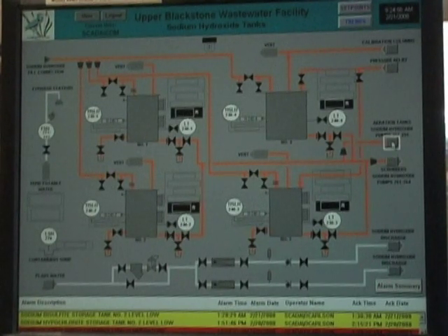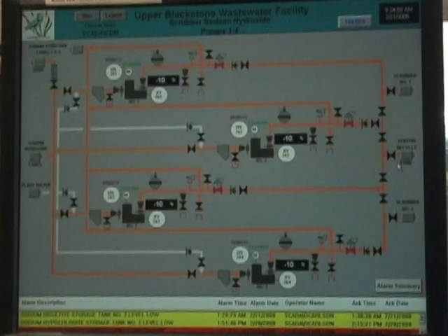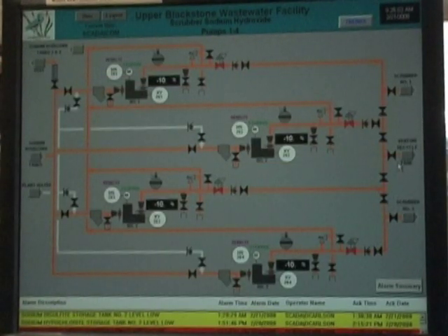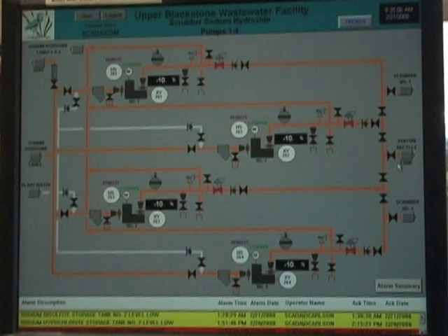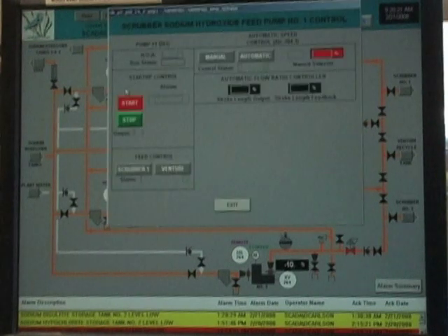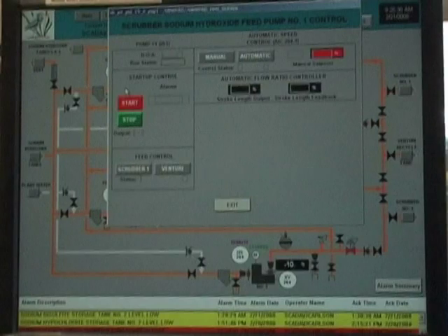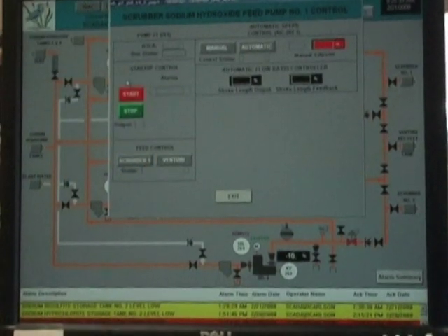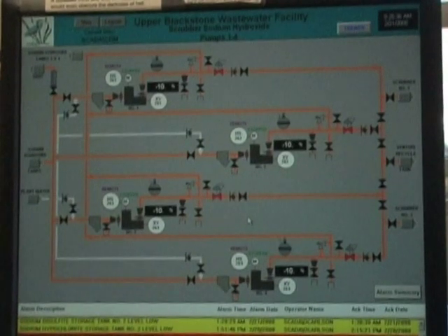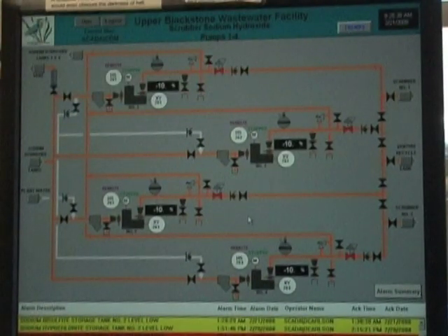If we go from here to the area to the scrubber sodium hydroxide pumps, you'll see the 4 new pumps that are going to be feeding into either the Venturi recycle tank or the 2 scrubbers, scrubber 1 or scrubber 3. Now the 4 pumps can go in many different modes. Currently we're going to talk about the automatic sequence, which you can bring up by clicking on the control screen here. We have start-stop control, we have manual automatic speeds, and we have to select where that pump is pumping to by using the scrubber or the Venturi. From here, they go out to the various injection points.